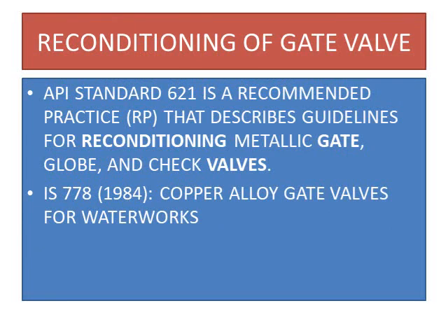When valves are used in industries, they are prone to maintenance, so wear and tear occurs, and finally maintenance is carried out on the valves. Reconditioning of gate valves is carried out as per API standard 621, which is a recommended practice that describes guidelines for reconditioning of metallic gate, globe and check valves. IS 778-1984, copper alloy gate valves for water works, are reconditioned as per this.